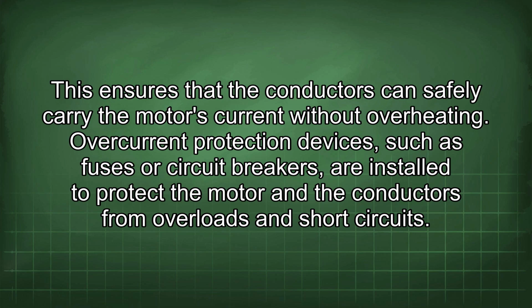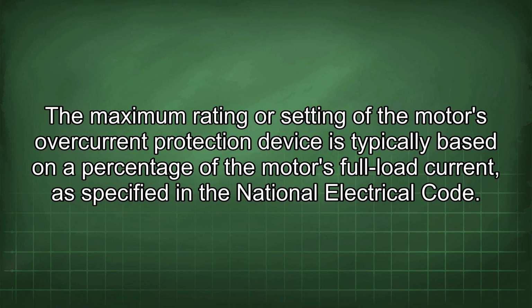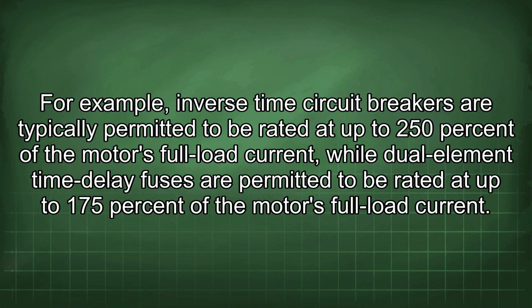Overcurrent protection devices, such as fuses or circuit breakers, are installed to protect the motor and the conductors from overloads and short circuits. The maximum rating or setting of the motor's overcurrent protection device is typically based on a percentage of the motor's full load current, as specified in the National Electrical Code.